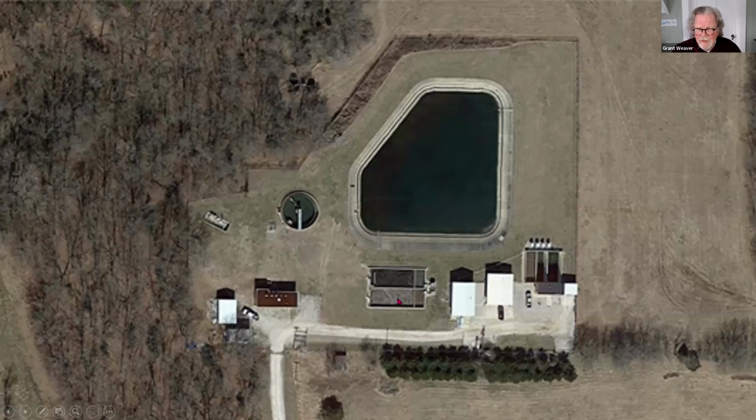So the sludge from the SBRs is wasted over here to the digesters. They're aerated, or they historically were aerated. And then, I don't know why, but Bruce let me talk him into the idea of dropping a submersible pump into one of the digesters, running that with much less air, so that sure, he could aerate it every day to keep it mixed, even aerate it for more than an hour at a time, as long as there were long air-off cycles to create the septic conditions.